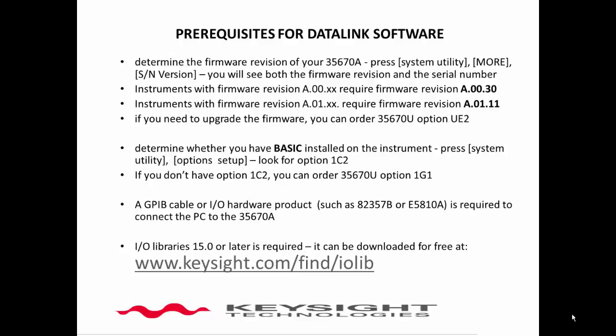The second prerequisite is that the instrument must have the basic option installed. In order to determine if the basic option is installed, push the System Utility hard key located under the display, then push the F5 key, which is next to the soft key labeled Options Setup. If basic is installed, you will see it listed as option 1C2. If you do not have basic installed, you can purchase it by ordering part number 35670U, option 1G1.